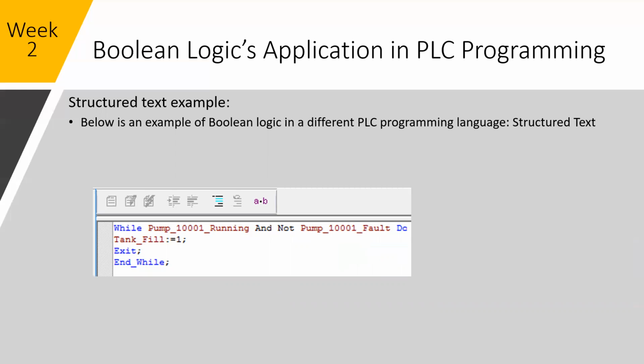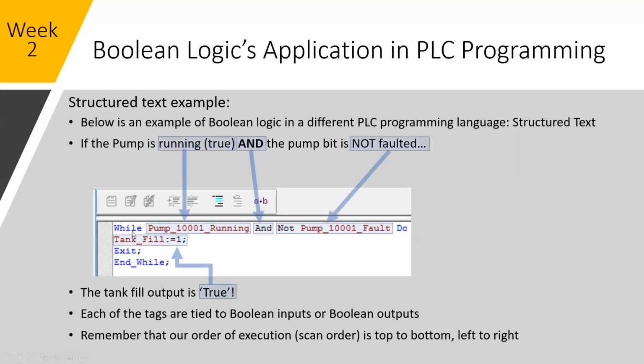Structured text example, Boolean logic in a different PLC programming language. It's all very much the same. If the pump is running and not pump fault, do fill tank equal 1. If true, if the pump is on and the pump isn't faulted, fill tank equals 1. So fill tank is a bit, a bool. All of these would be bools. Fill tank could be triggering another function of code, could be running a pump, or just saying it's in the state of filling the tank. Does that make sense?